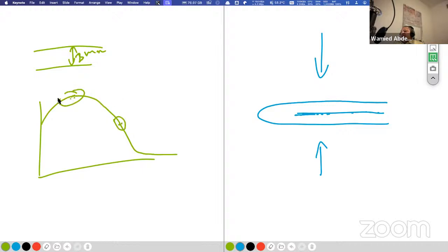Because here there is a higher chance of losing the signal due to recombination because of the high density of ions, compared to when we are in this region. So if we just take the pure signal without any corrections, definitely the PDDs that we're going to get are going to be wrong. They're not going to be the true doses, the true PDD, because we are having an under response of the chamber here compared to here.